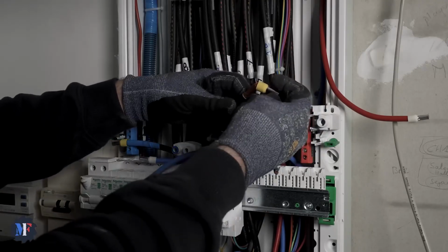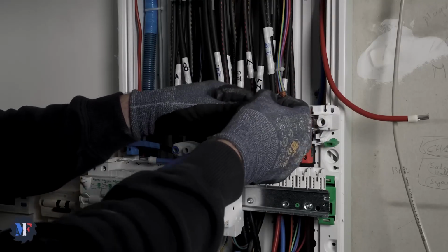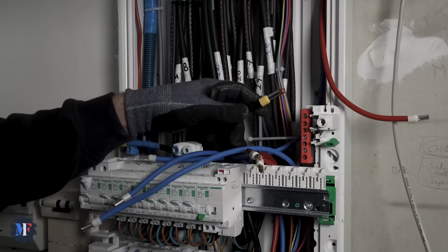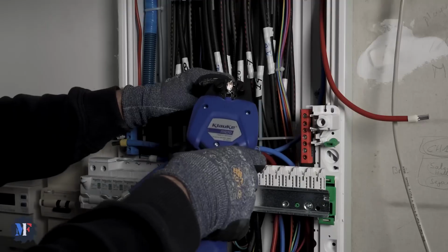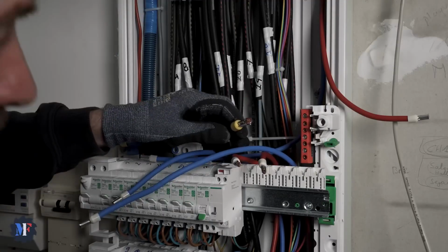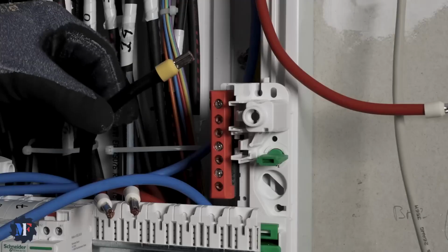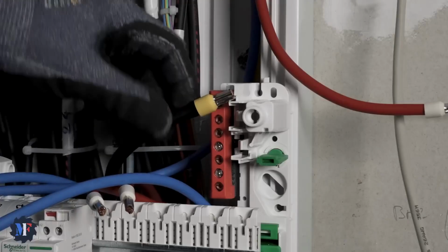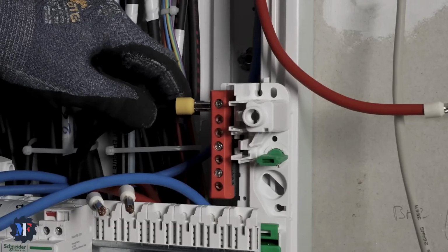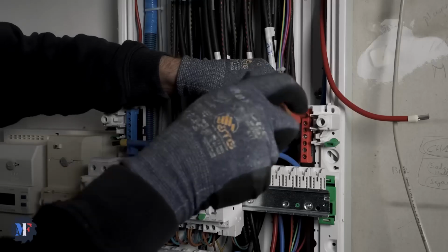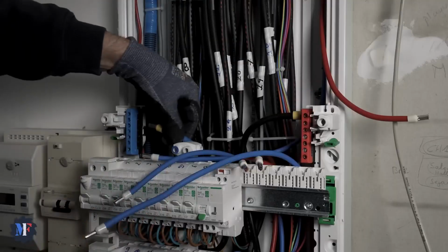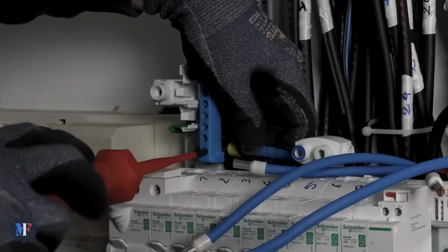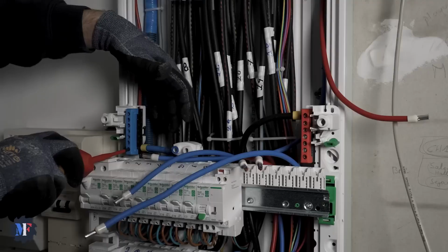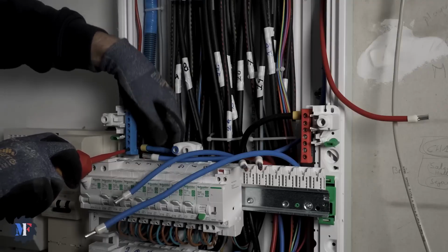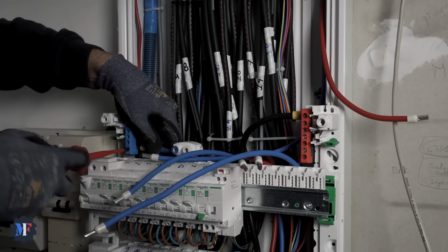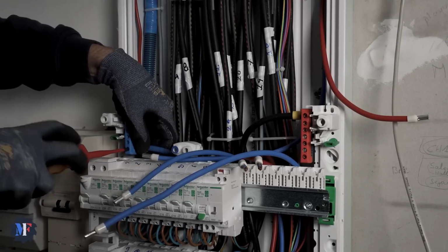So, it's yellow. You can repaint it black if you want. You can put some red tape on it to represent the phase, we crimp all of this. We're going to cut off the excess. So this one, it's going to come here, on my phase terminal block at the location for the 25mm diameter. That's done. We do the same for the neutral, placing it at the bottom since it's reversed. You need to hold them securely to ensure a proper fit, and above all, here it's just plastic, so I hold the terminal block while screwing to avoid breaking the tabs.